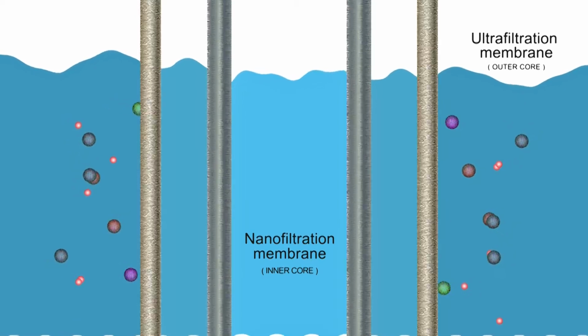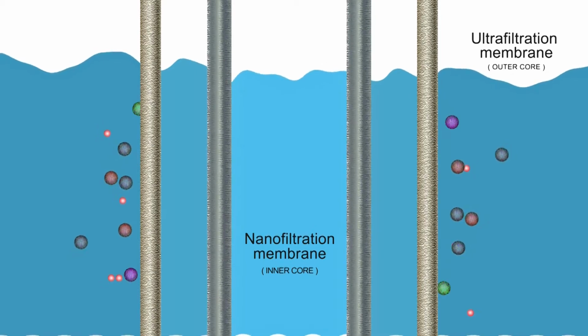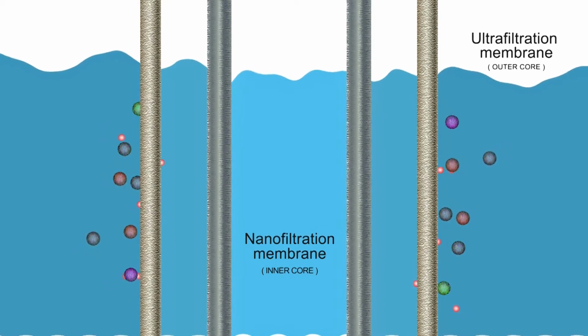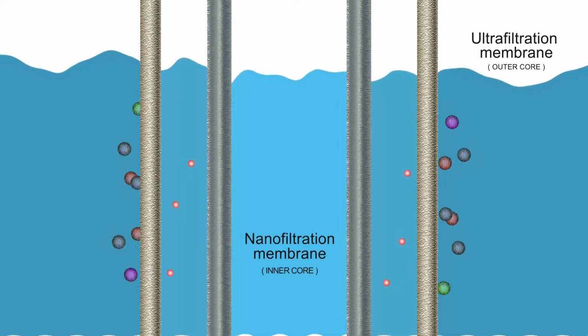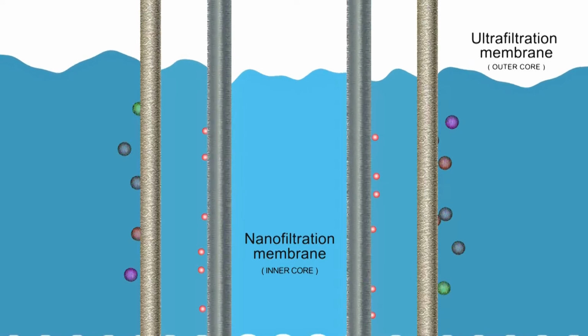After passing through the guard strainer, the water is dispersed through a manifold of UF membranes. Differential pressure forces water and particles smaller than 0.1 microns through holes in the membrane fiber to the inner core. Another differential pressure is created, this time separating the particles which are even less than 0.1 microns in size. This filtered water can then be discharged or sent to additional processes. Suspended solids and other contaminants, including bacteria, protein, or viruses, are filtered out through the membrane fiber outer core.